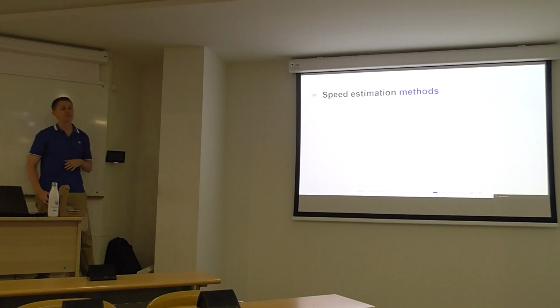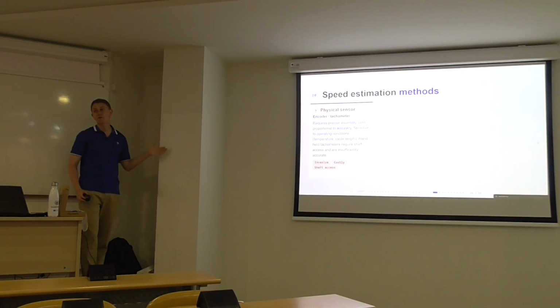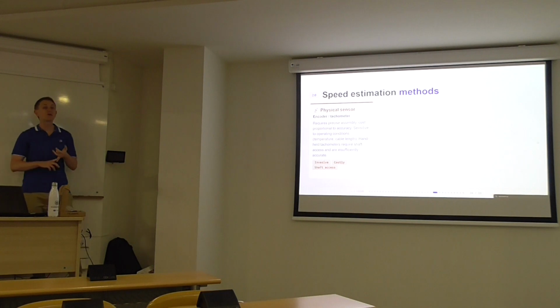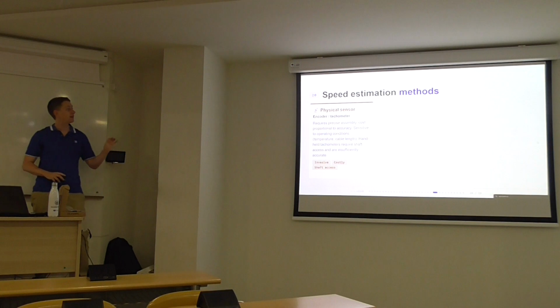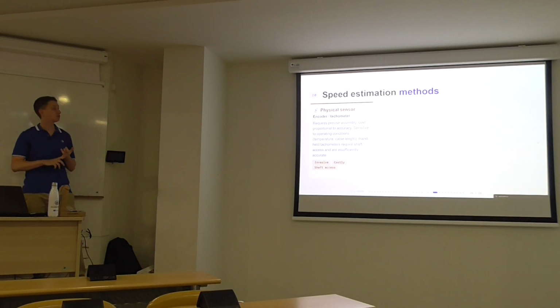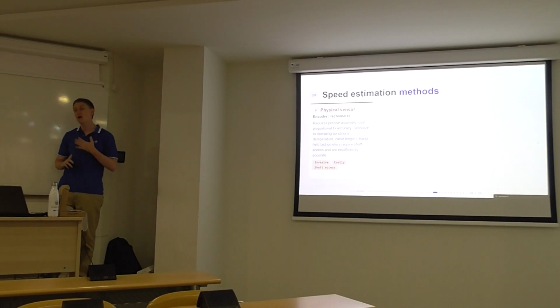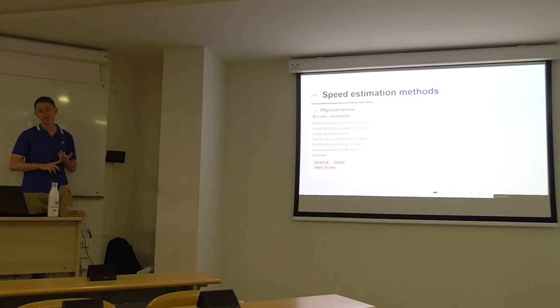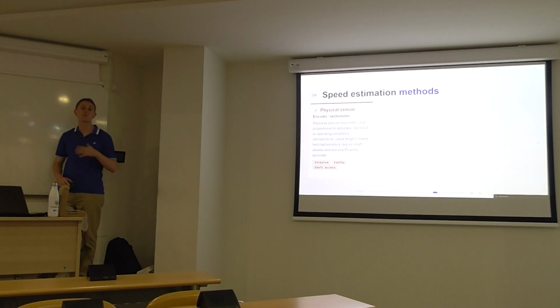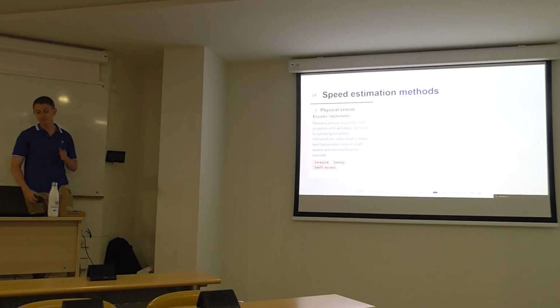So, what speed estimation methods do we have? Of course, physical sensors, an encoder or a tachometer. An encoder requires precise assembly and its cost is proportional to accuracy. Also, it is sensitive to operating conditions, while a handheld tachometer requires the shaft to be accessible. So this is not always possible.